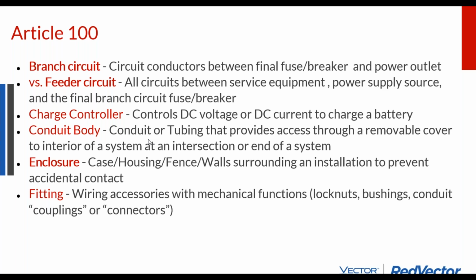Enclosures, so housing, fences, walls surrounding to prevent accidental contact. The good rule of thumb is, your electrical devices need to be protected and safe and enclosed. Those enclosure requirements ramp up with higher and higher voltages. And where the code is going is that manufactured, stamped, listed, assembled parts like the Tesla Powerwall will have different, more lax electrical code requirements than if you decided to build your own battery pack out of listed batteries and put them on a shelf.